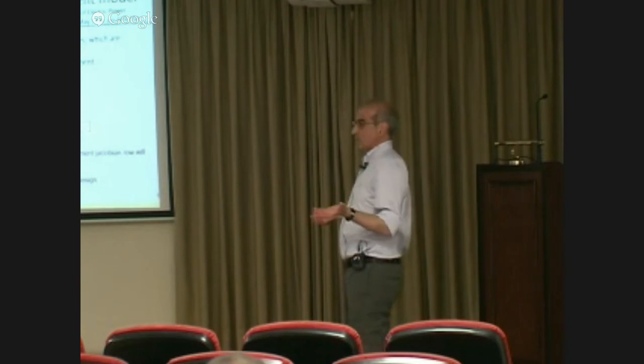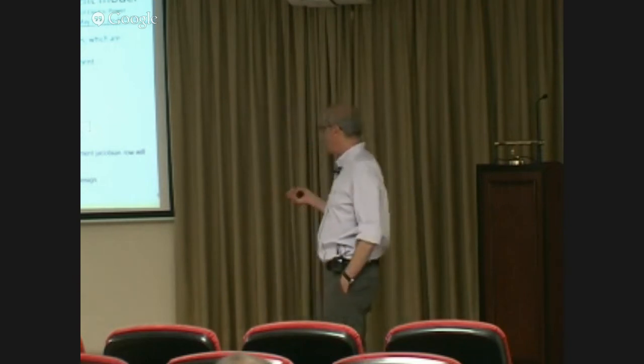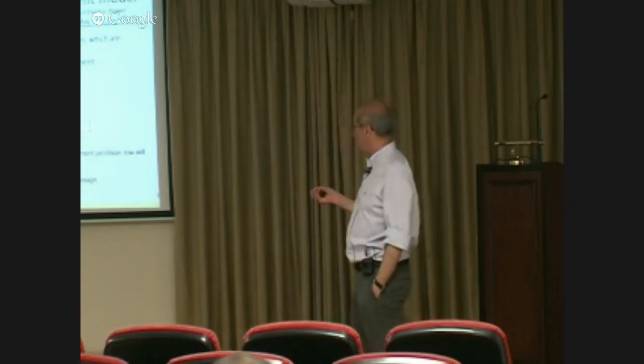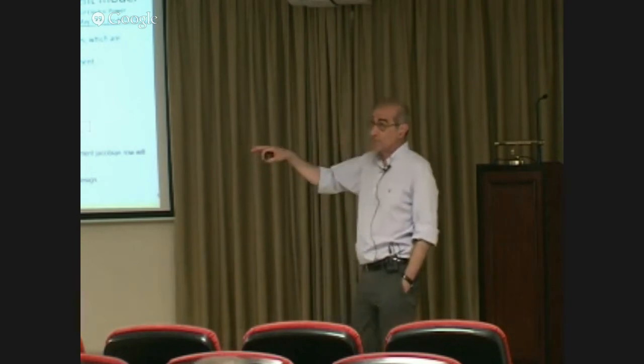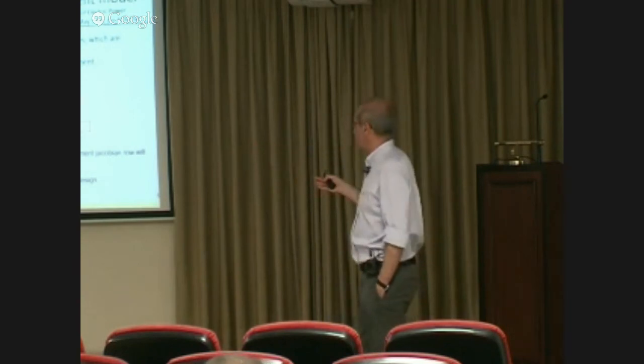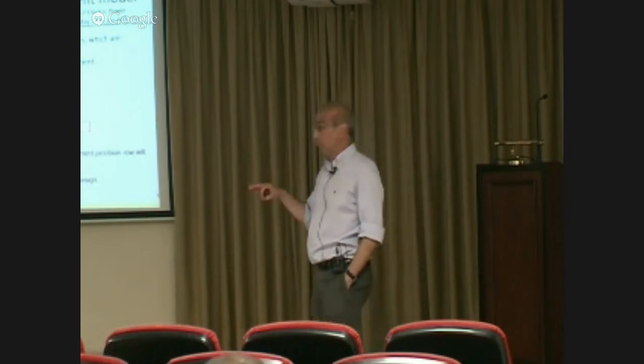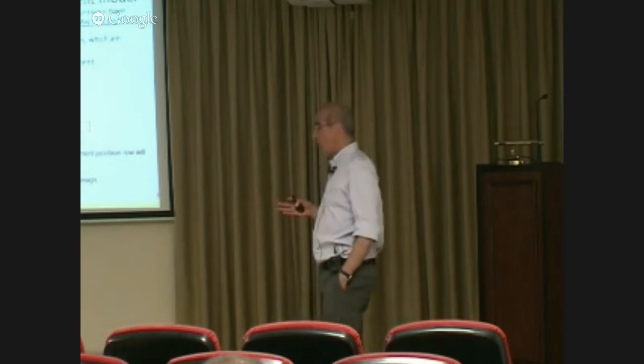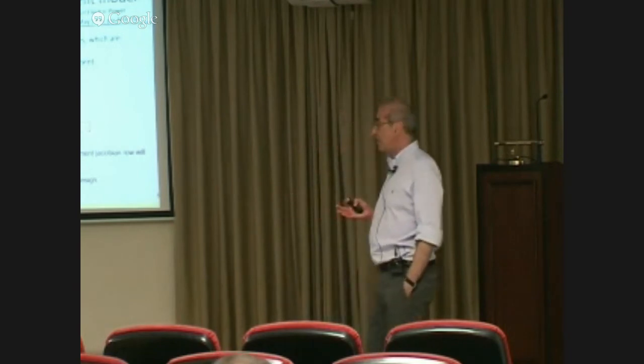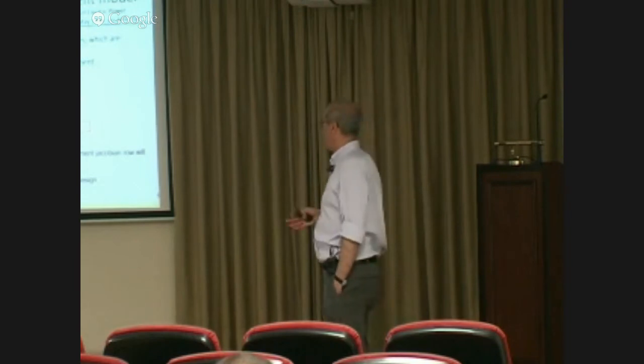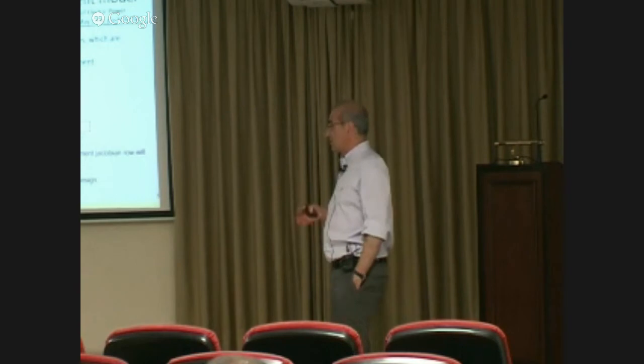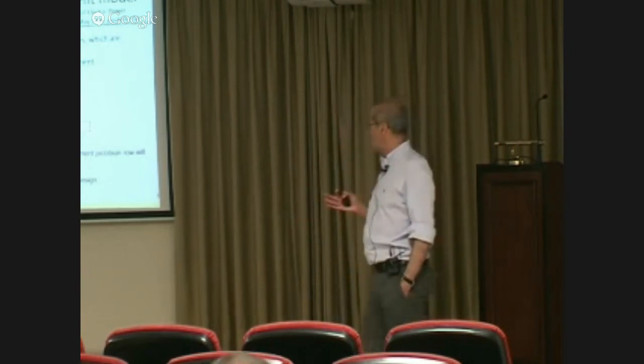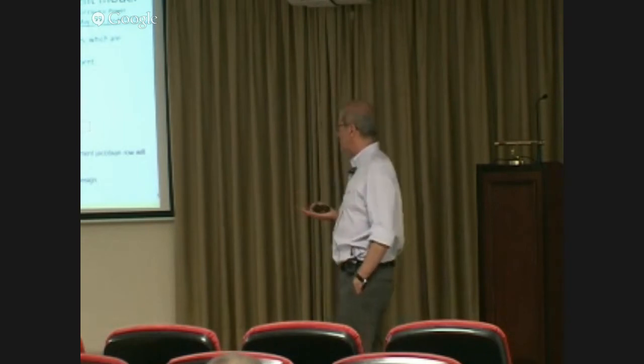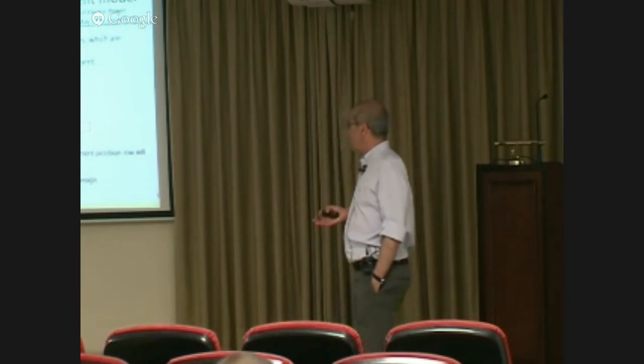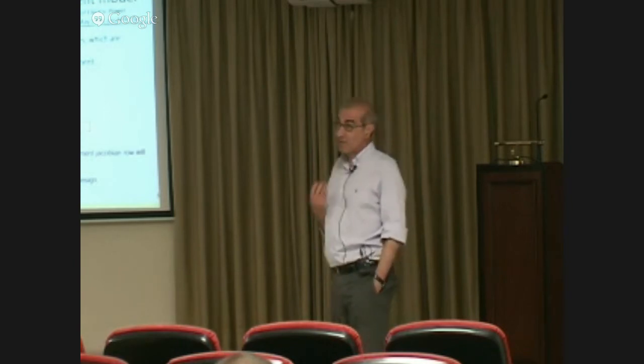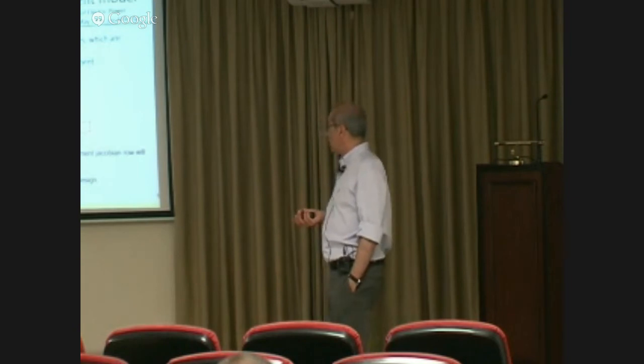For instance, if you consider an injection measurement, typically you have a large value in one of these entries, and the others will be much smaller. And it's not an easy task to bring them all down to a reasonable level. In the case of flow measurements, you have a way of doing it by scaling, but for the injections, definitely you cannot do it. Also, in general, for the nonlinear solution, from one iteration to the next, these things may change. And handling these and getting rid of leverage measurements is a problem. Now, if you consider PMU measurements, phasor measurements, instead of SCADA, things suddenly change.